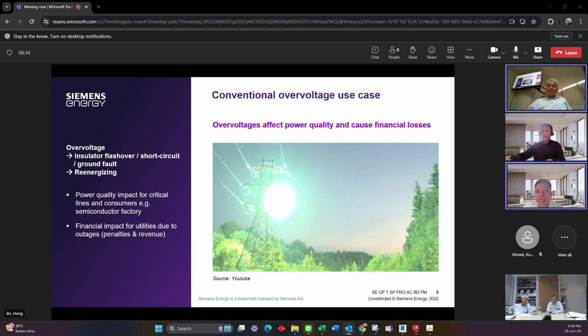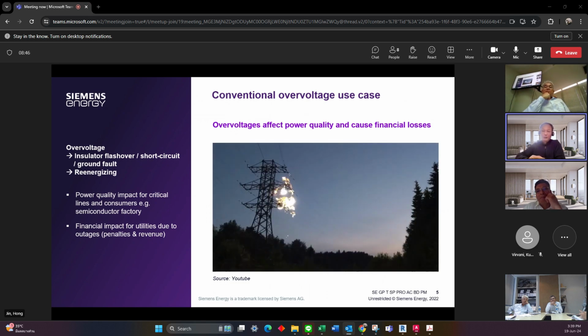Is there no sound? Unfortunately, the sound is not so easy to transfer to your side. But the most important is the video, the picture. It also shows the same flashover on the insulator three times. So if a lightning strike hits the overhead line, the shielding wire, or the tower body itself, then the insulator will suffer a very high overvoltage. And if we also have a very critical footing resistance, it will often lead to a flashover on the insulator. Just like the video shows, this is one flashover with three slow-motion playbacks.